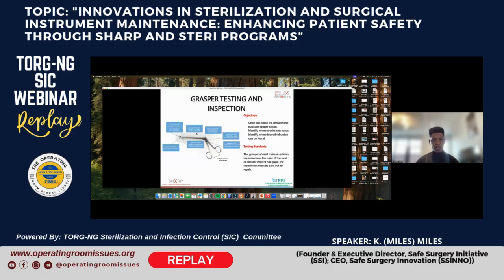Here we have a grasper. Sometimes it's called a pituitary grasper, the different versions of it. As you can see, we're going through similar inspection points. We're looking at the jaws, making sure they're meeting properly. We're going along the shaft of the instrument, making sure there are no signs of damage and wear. We're looking at all of the articulating parts, all of the moving parts that should open and close, and how they interact with the distal side of the instrument. So you want to check all of these different inspection points to make sure that instrument is going to function properly during surgery.